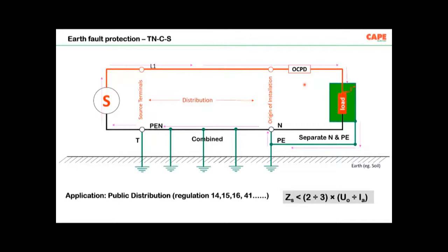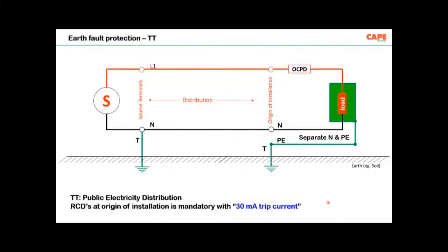Remember, for earth fault protection, RCD is an additional protection. It is not the primary protection. Primary protection is your fuse or MCB. So the earth fault loop impedance of this particular circuit must be low enough so that higher current flows and disconnects the MCB, and the calculations are given in the standard.